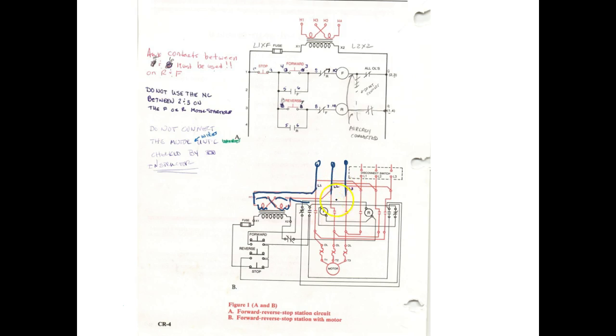And some of y'all are using L1. Then I'm going to take L1 right here, right? This comes down to my L1 contact on my motor starter. This comes down to my L2 terminal on my motor starter. This comes down to my L3 terminal on my motor starter.